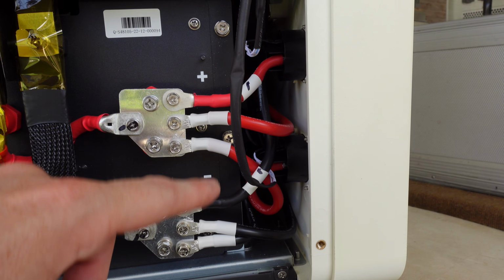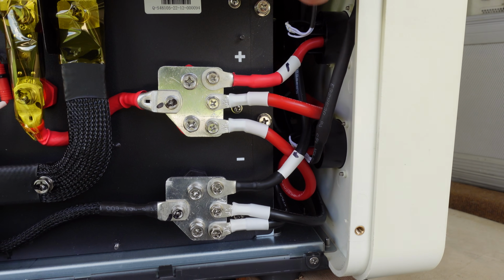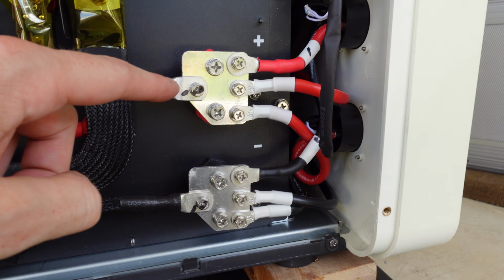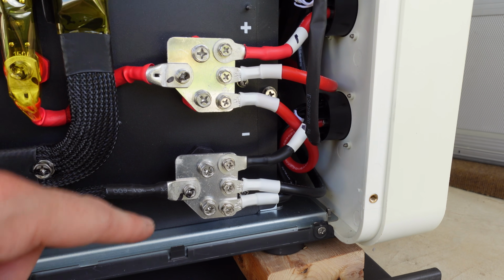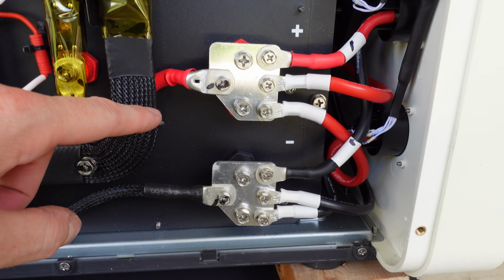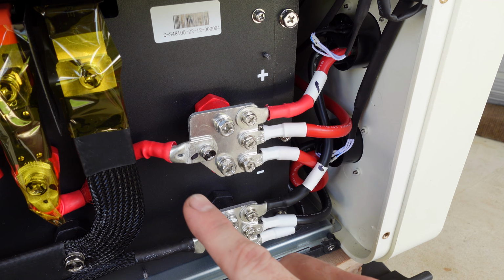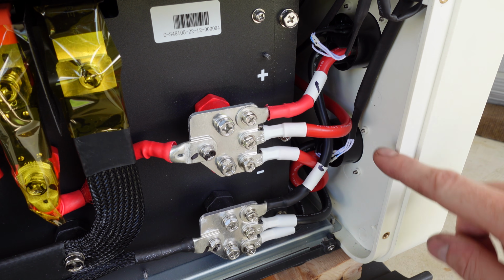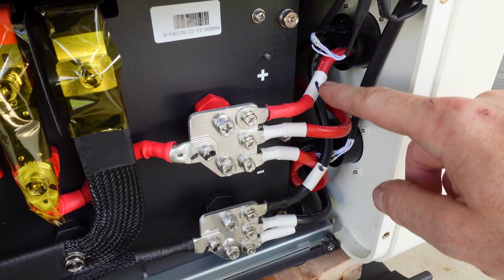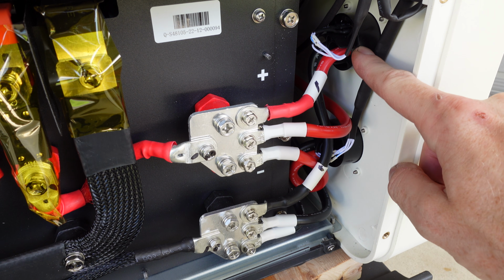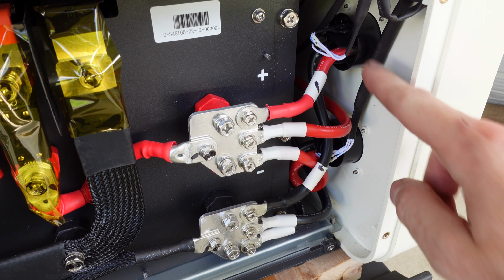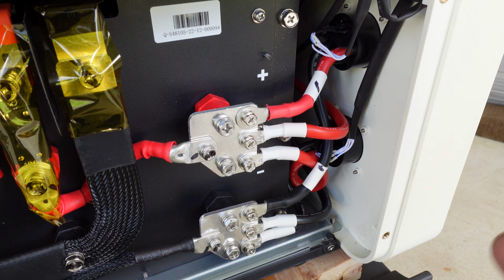This is all done with 6-gauge silicone insulated wire, rated for 200 degrees Celsius insulation. You can see we have 3 connections for both positive and negative, actually 4 if you count the ones on the left. This is power coming in from the battery, and then we have 3 leads coming out of each bus bar: one set going to both front battery connectors, and the third lead going up to the inverter charger.